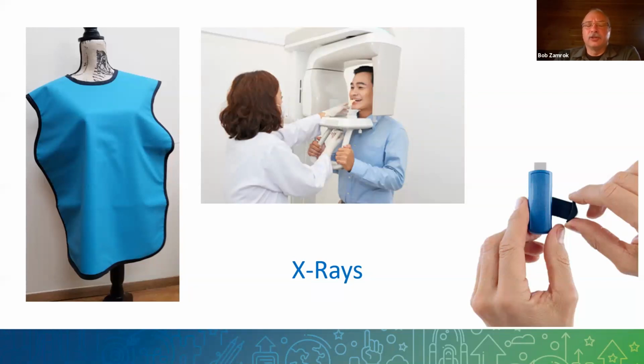Every office needs to, at least once a month, take an image for QA, and you need to store that on your workstation for your 3D machine so that when the inspector comes in once a year, well, in New York State it's once a year, I think Pennsylvania is the same way now, they're going to ask to see those tests. So you're going to need to go to this file and say, okay, here's 2021, these are all my QA tests and everything passed.